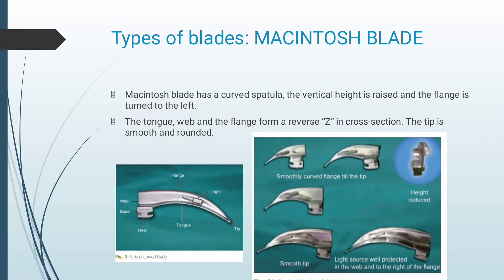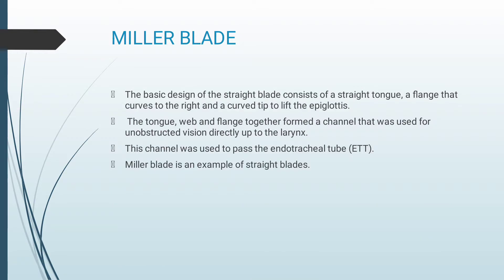To name a few types of blades: the Macintosh blade, which has a curved spatula. The vertical height is raised and the flange is turned to the left. The tongue, web, and flange form a reverse Z in cross section. The tip is smooth and rounded. The Miller blade — the basic design of a straight blade — consists of a straight tongue, a flange that curves to the right, and a curved tip to lift the epiglottis. The tongue, web, and flange form a channel for unobstructed vision directly up to the larynx, and the channel is used to pass the endotracheal tube. The Miller blade is an example of straight blades.